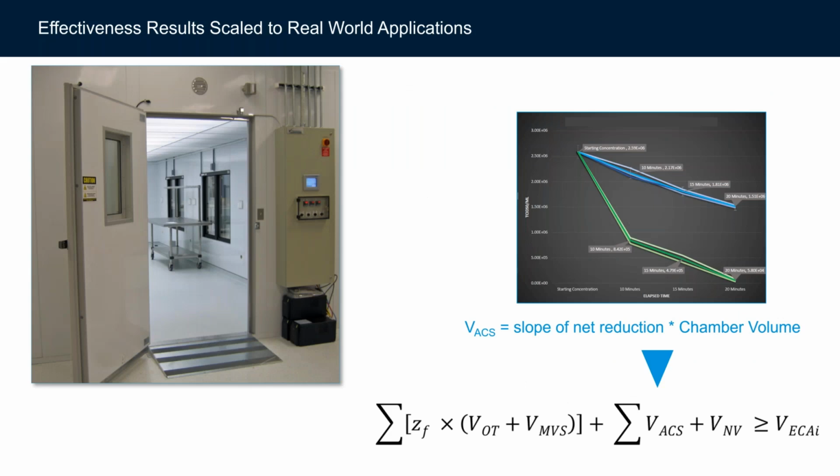This is what the chamber could look like. This is one example of one of the chambers in one of the third-party tests. And what I want to point you to when you look at the test is when you get the results, there's a handful of things you want to understand about the results. One, was it done in triplicate? You can see the 3 lines there.